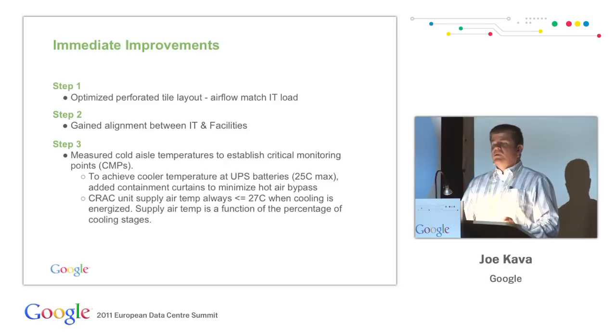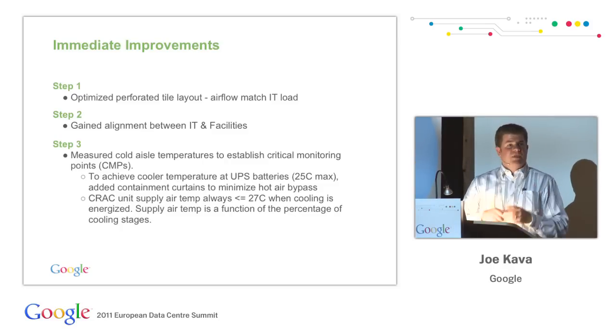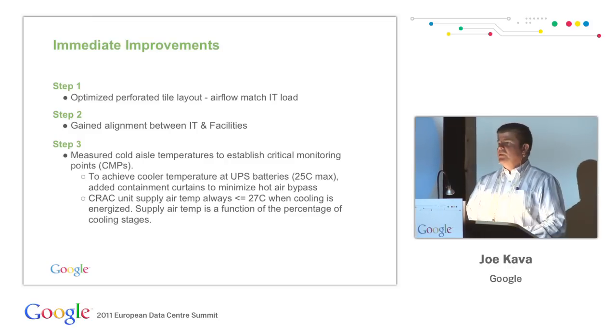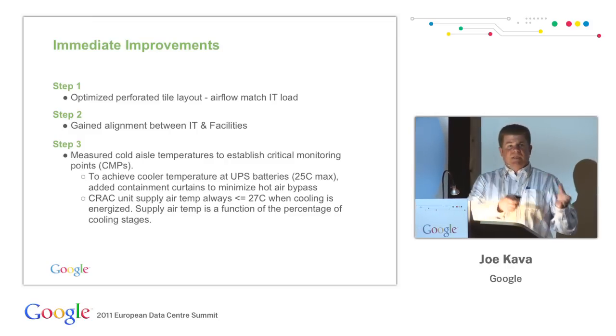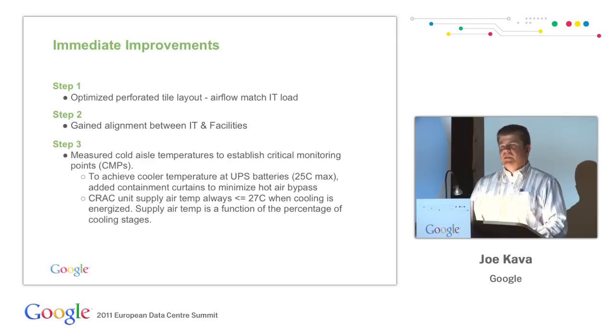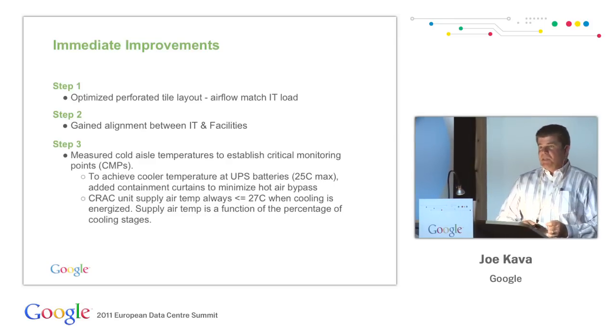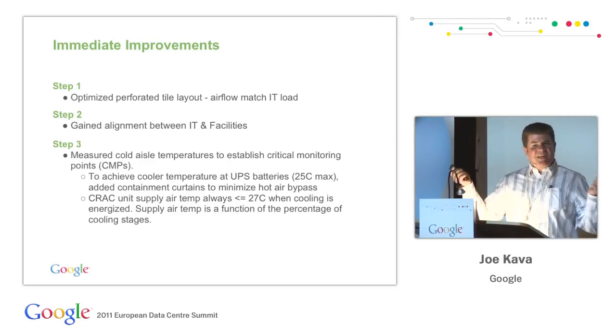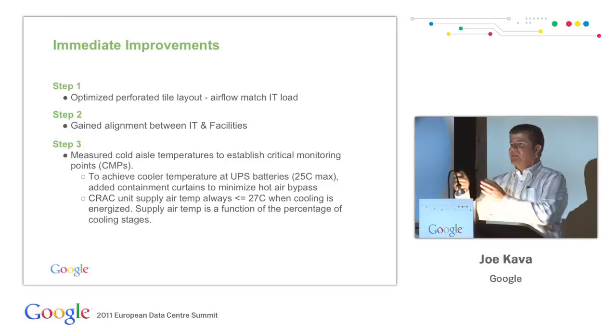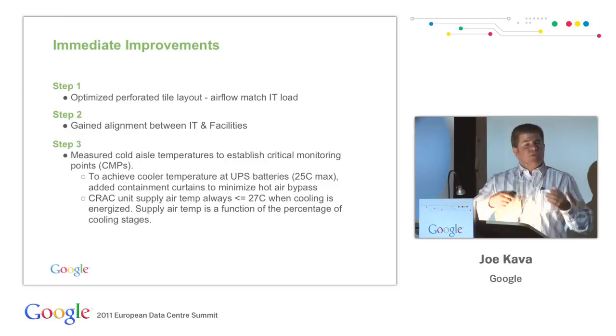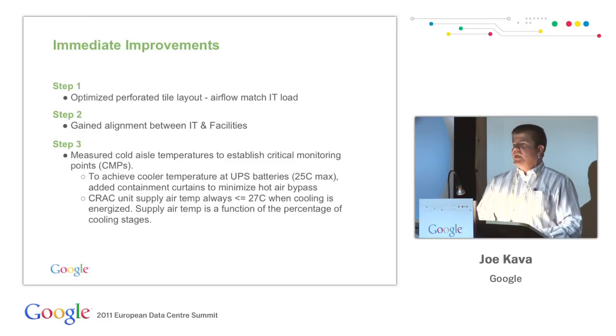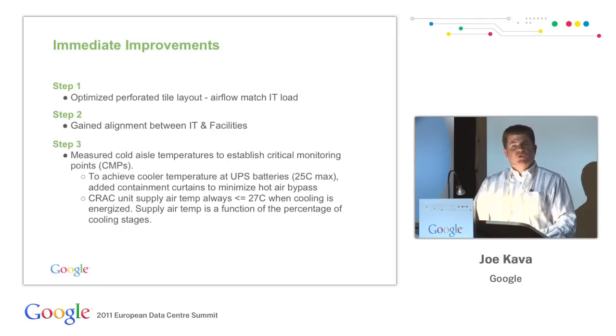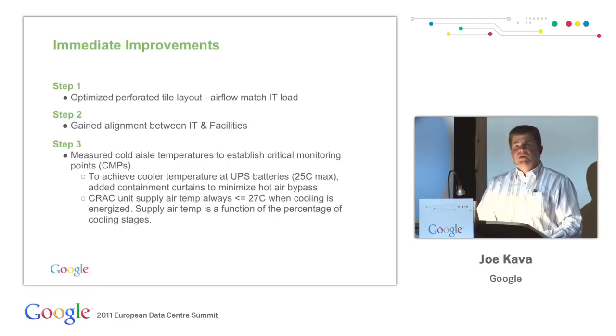The first was to optimize the airflow coming out of the perf tiles. So optimize the perf tile distribution so that you're balancing the cooling with where the heat load is. The second thing was that we have business units that were responsible for these network pops. So we went to the networking team and the Corp IT groups. We got their alignment to really get their buy-in to start operating these rooms at the expanded ASHRAE recommended range for both temperature and utilizing the full range of recommendation for humidity control as well.